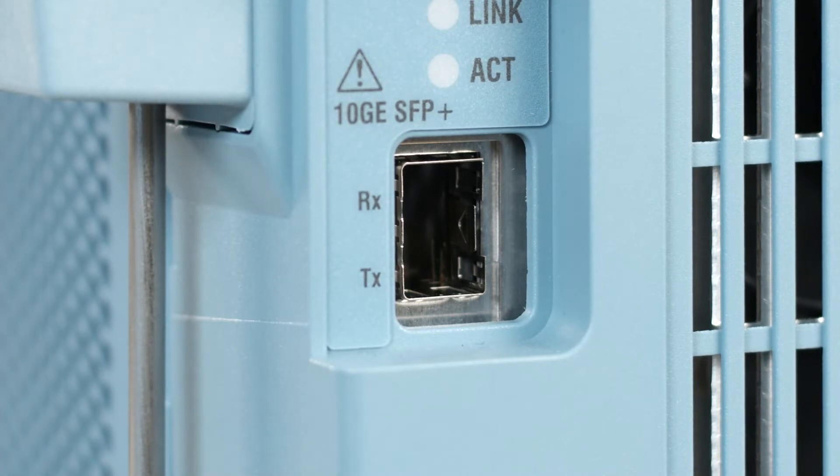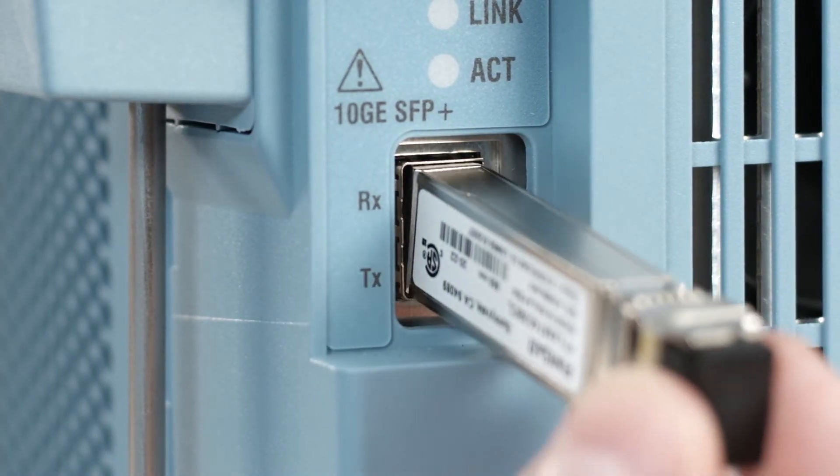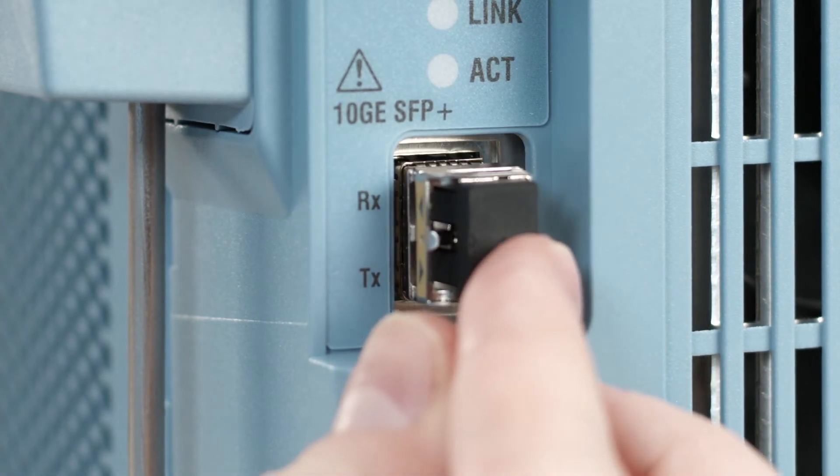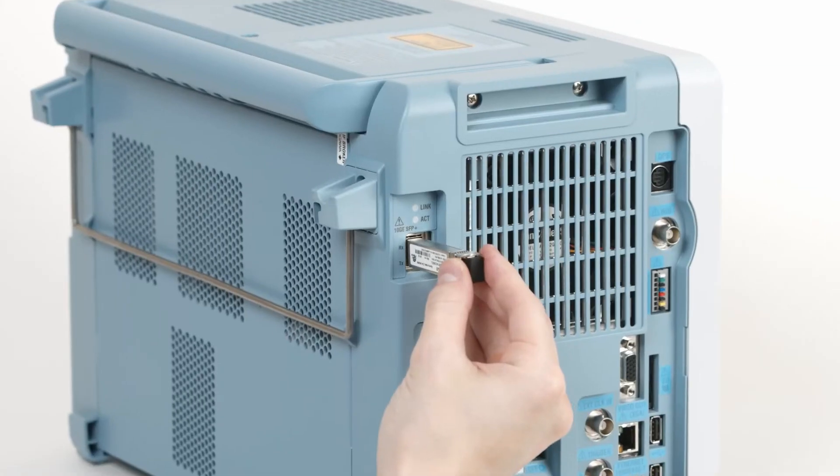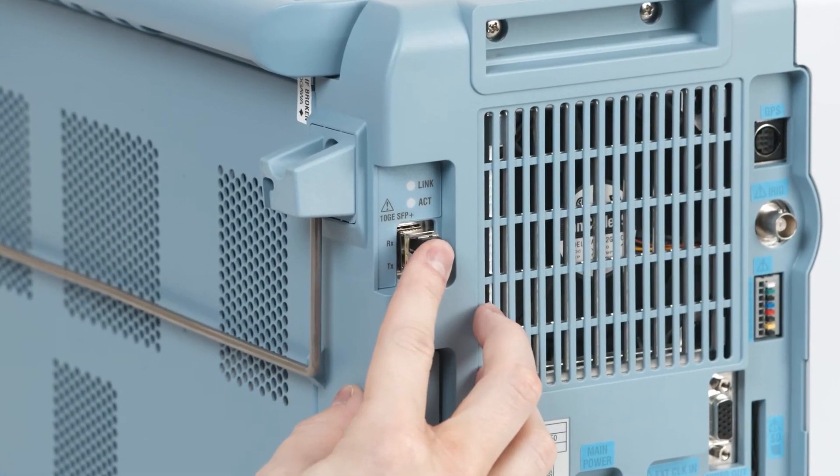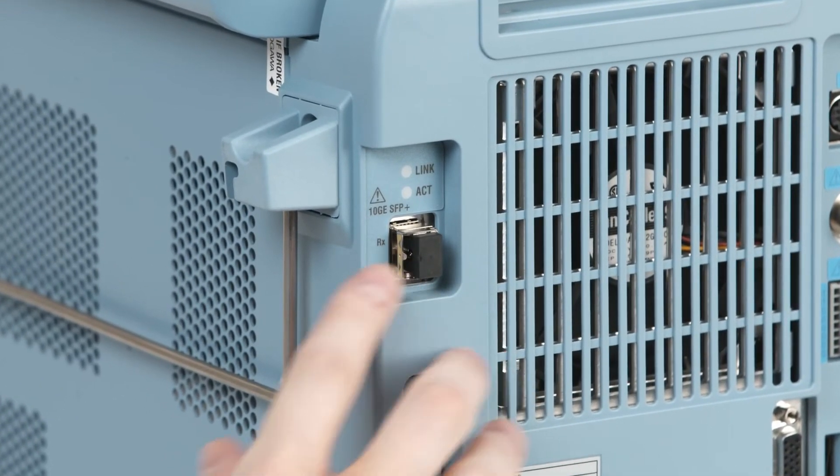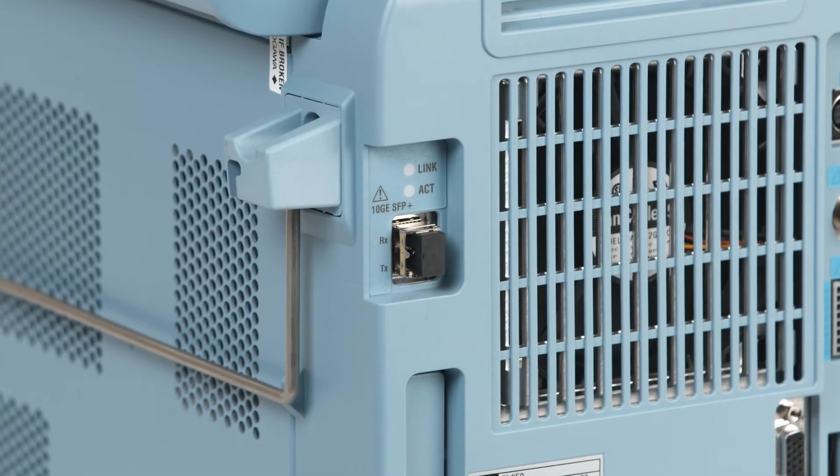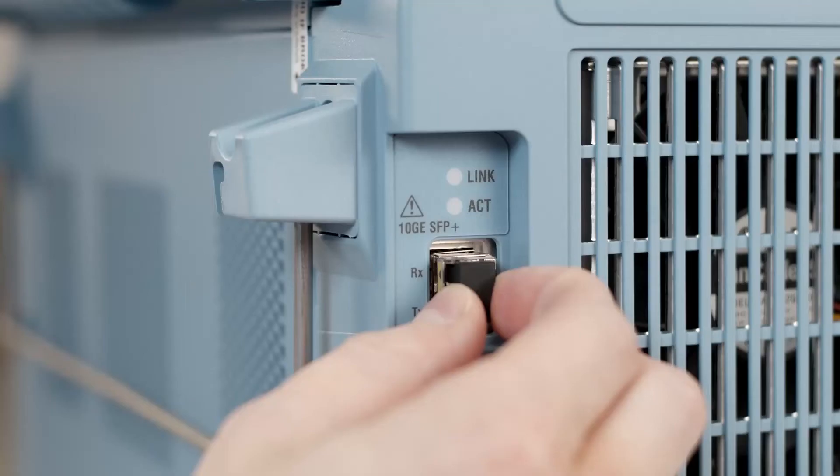Position the module so that the TX and RX markings on the instrument align with the arrow in and arrow out on the module and push the module inwards until you feel a light click. Be careful not to damage the electrical terminals and if you feel too much resistance, remove the module and try again.